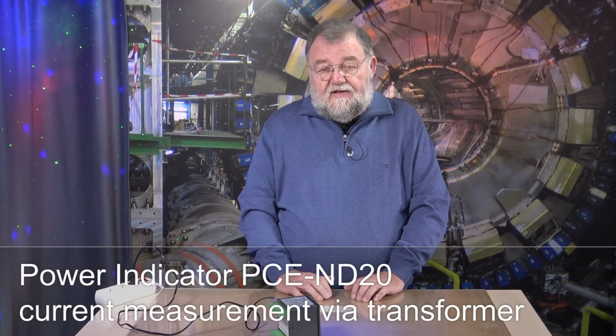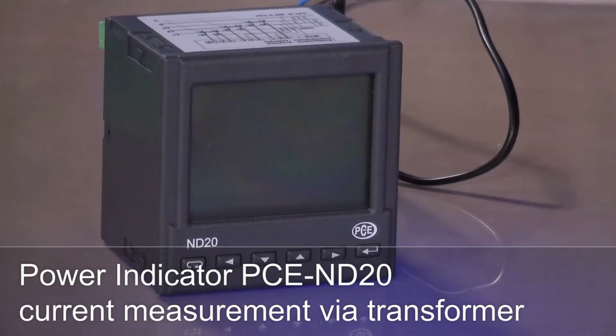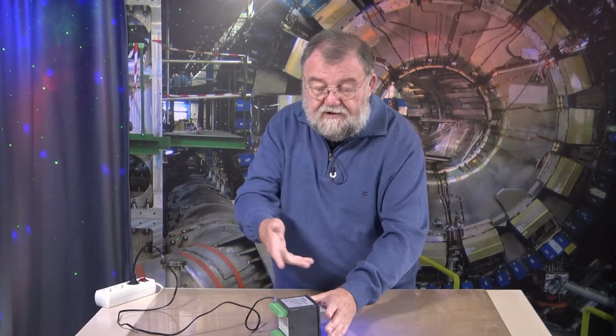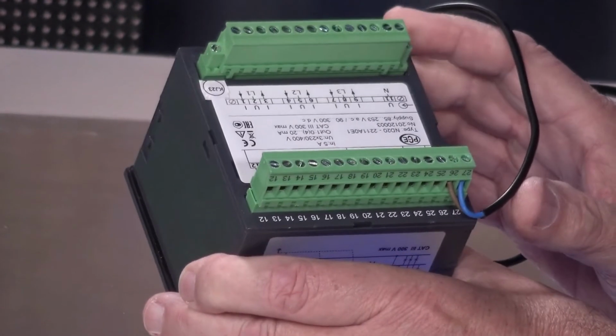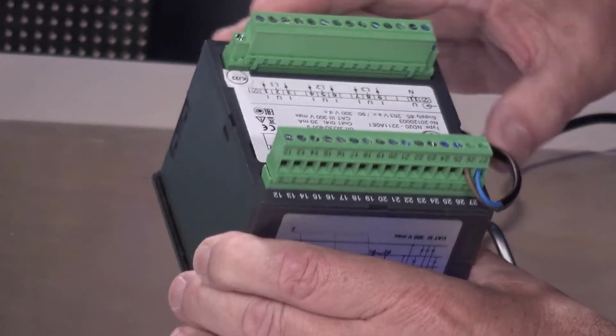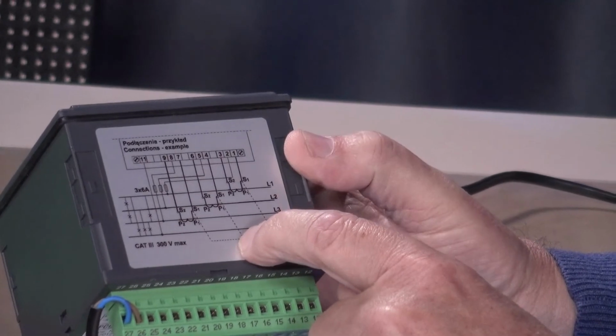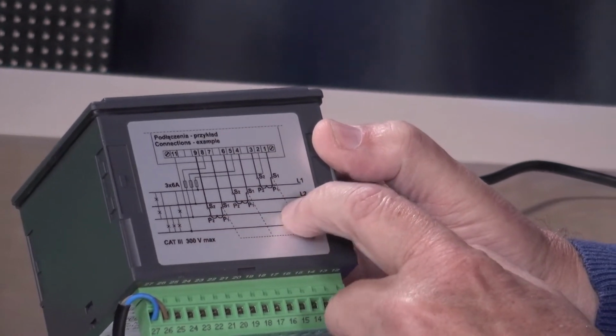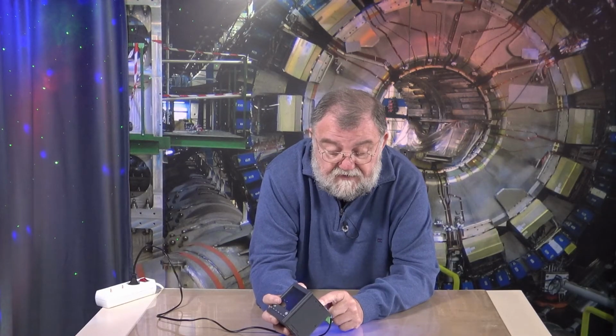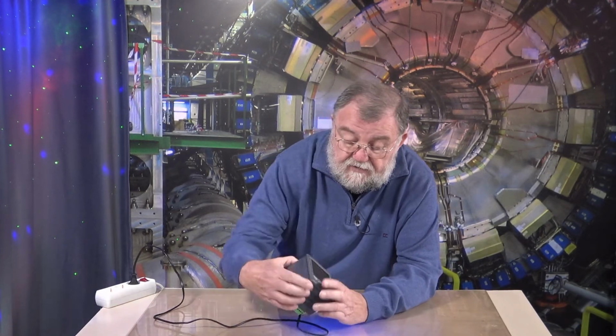The ND20 from PCE can be directly built into a switchboard. On the front side it is IP67. The reverse side is clear - you have the connections. It looks like this, here's the description of the in and out connections. I can see straight away where L1, L2, L3 are, where N is connected and so forth. I have the possibility to see my measuring transducer, what I can connect, so that over the transducer I can measure grid flows. It's also shown here - no problem for a professional.